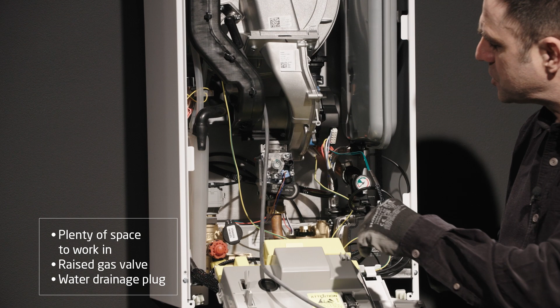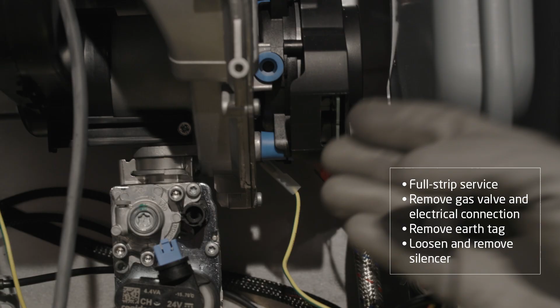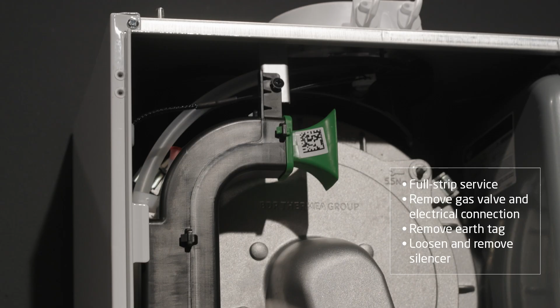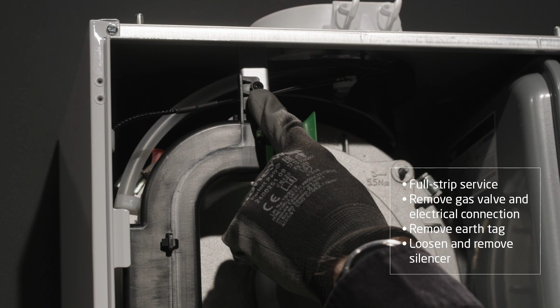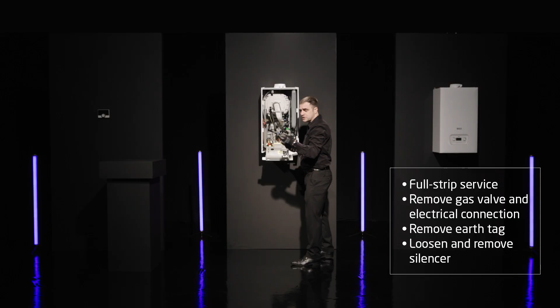Remove any chance of that water getting into any components, any circuit boards, and damage them. Now, if I wanted to do a full strip service, I'd start by quite simply removing the electrical connection off the gas valve and the fan, not forgetting the earth tag. And then I would undo a connection here, a little screw there, and a screw there. That's for my silencer. Just loosen them off, you don't have to take them all the way out. Ease that to the side, and away it comes.